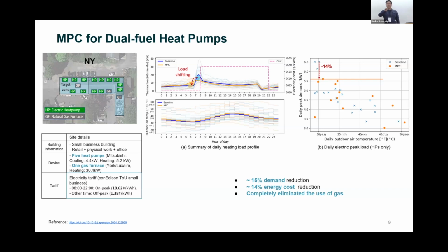What they are doing is, once the heat pump is not able to meet the set point or goes above the deadband, then it activates the gas furnaces. And this happens mainly during the setback period, where the set point changes and kicks in the gas furnaces, but the model predictive control completely eliminates the unnecessary use of gas furnaces. That's an important lesson learned and a feature.